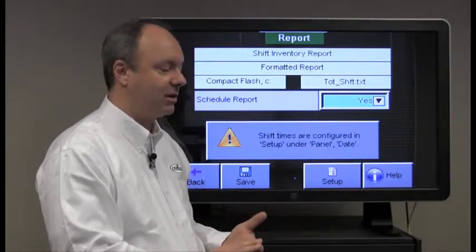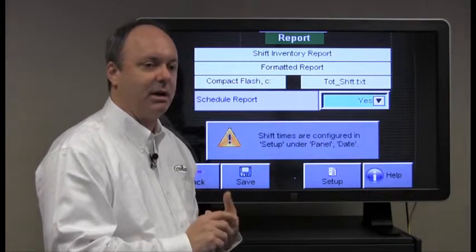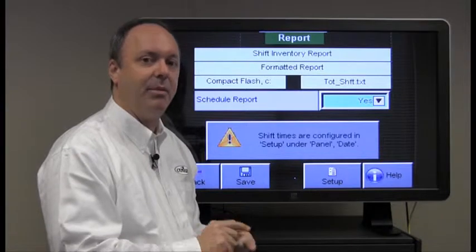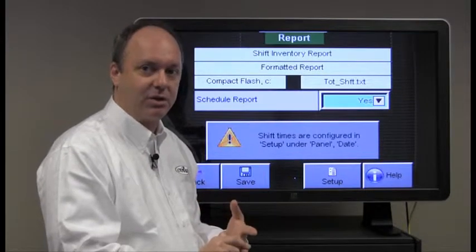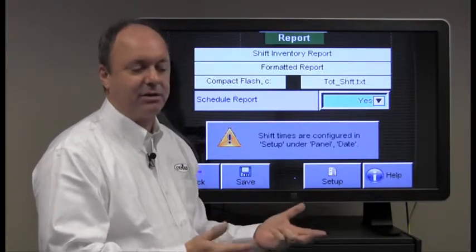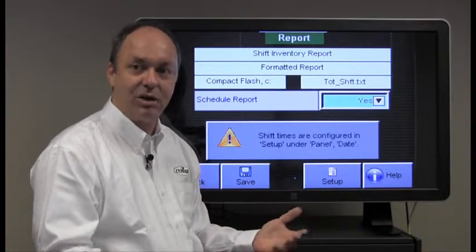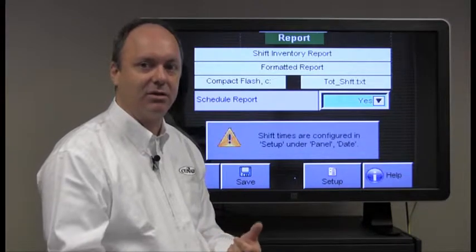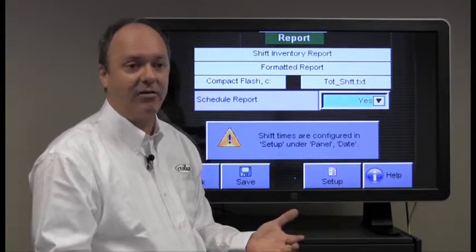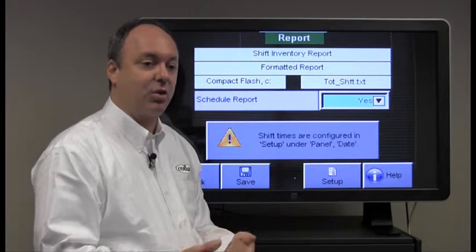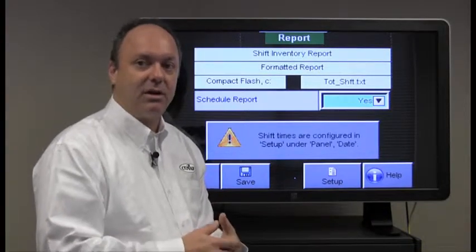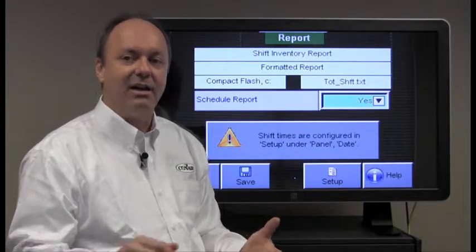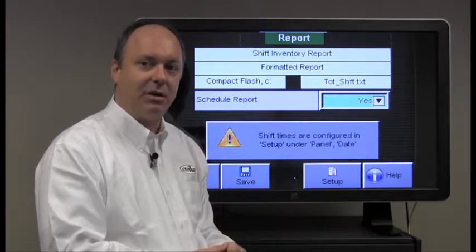So in that particular menu, you set up the shift begin time and then the duration of that particular shift. So if you have, for instance, three eight-hour shifts, then you would give it the start time for each shift and tell it that the duration is eight hours. You may have a factory where you have a shorter shift that's a third shift or a shift that overlaps into an additional day. So that's why we allow up to three different shift times to be defined.